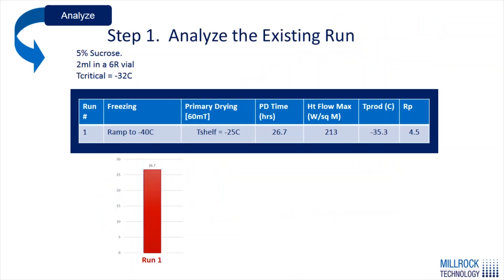The results from this run, drying at minus 25°C, show a primary drying time of 26.7 hours. That doesn't say much in isolation, but we'll see how this compares as we optimize the cycle in the following slides.